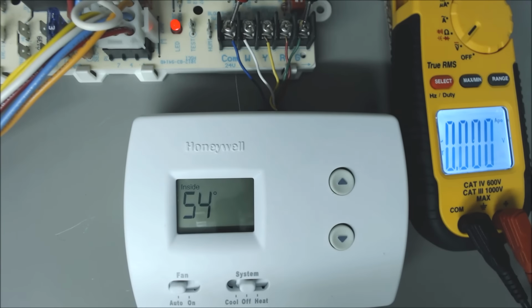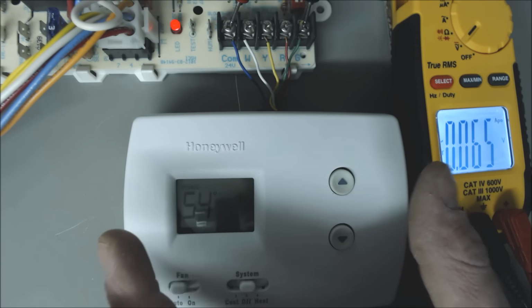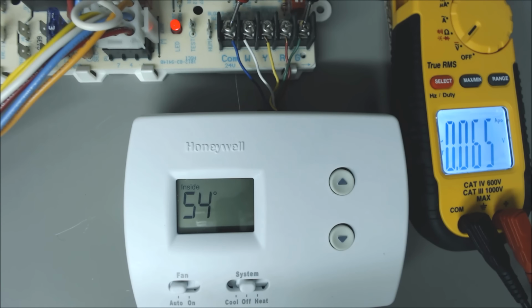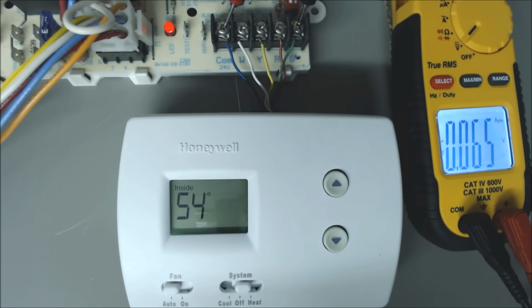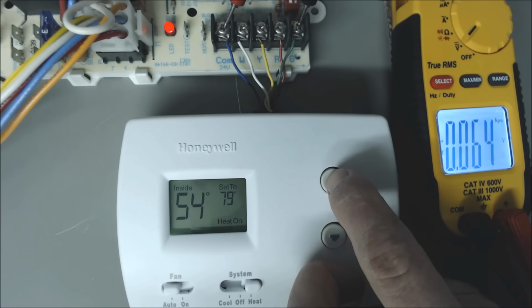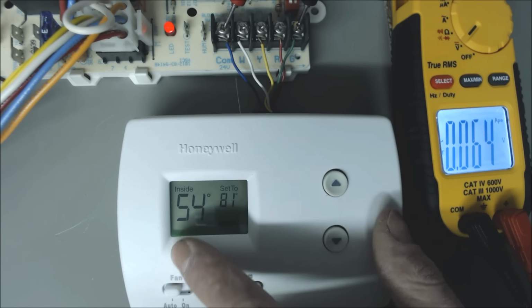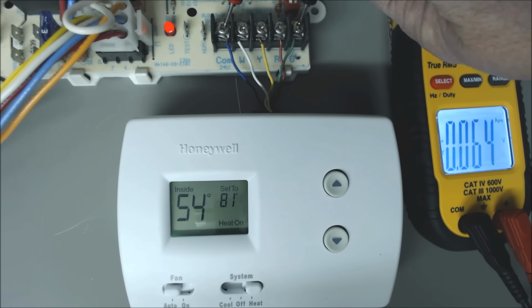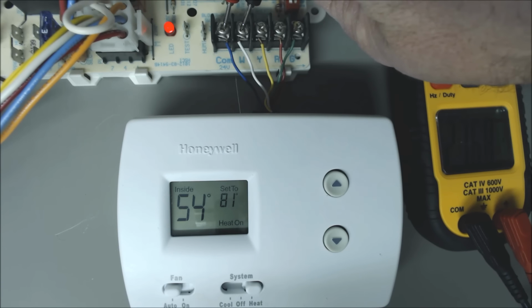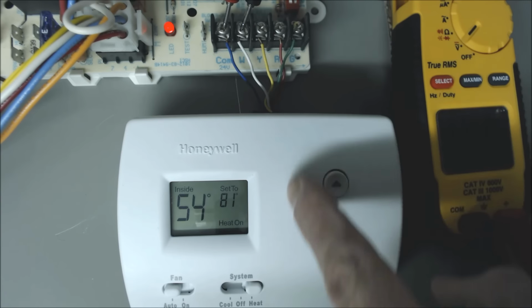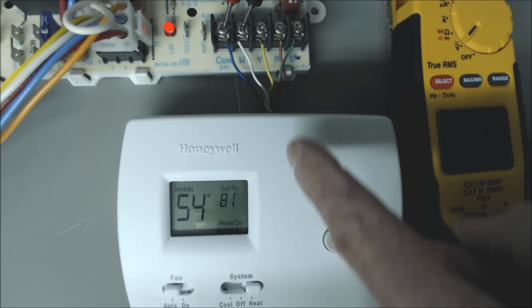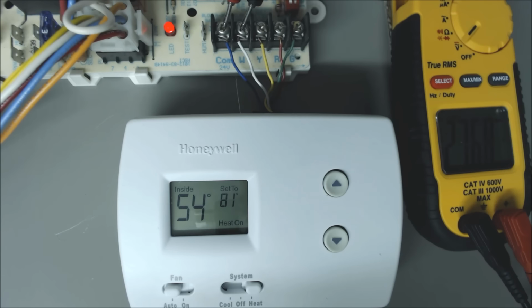Now I'm going to go ahead and turn the fan off, and you see that our voltage has decreased. So what we're looking at is reading 24 volts. Anytime we're talking about 24 volts, we're talking about 24 to 29 volts. Anywhere in there is good. Now if we want to check for heat, we're going to turn our thermostat to heat, making sure that we're reading a number higher than what it actually is in the room. Now we're going to leave the one probe on common, and move the other probe over to W. What this means is that R is coming into the thermostat and should be touching W and coming back to the control board.